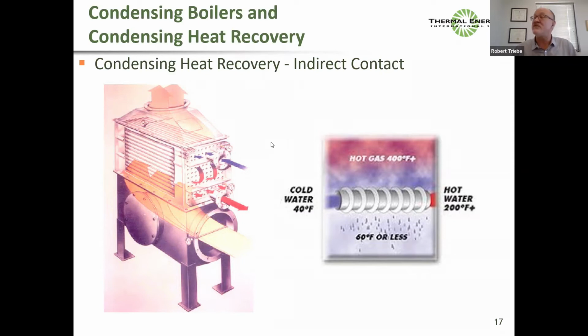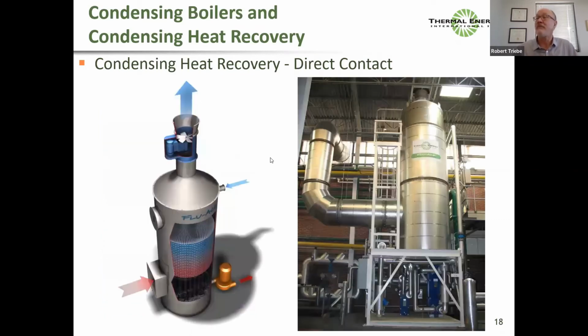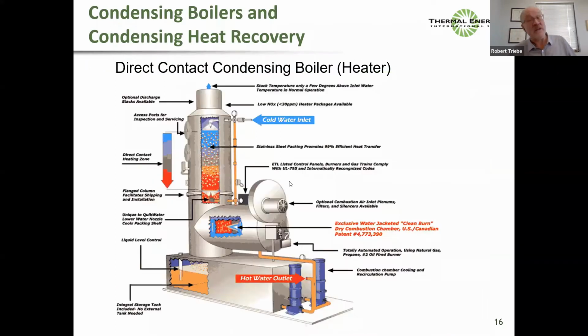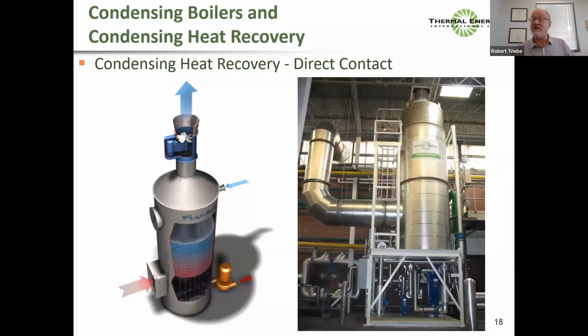Cool the gas to below its dew point to recover that latent heat, and you have to build accordingly, all stainless steel, no more carbon steel economizers if this is the goal. And now we have the direct contact condensing economizer, which is this without a burner. And we don't need a burner because we're using waste heat. So you take your boiler exhaust, you take your waste heat, you put it in here. It's a wet scrubber. Water flows through and heats up. And that's a direct contact economizer.